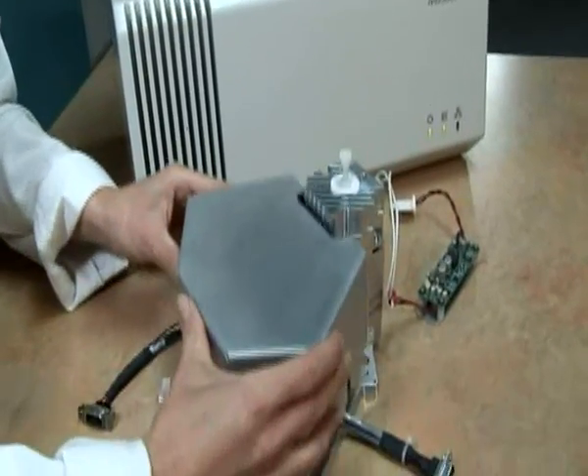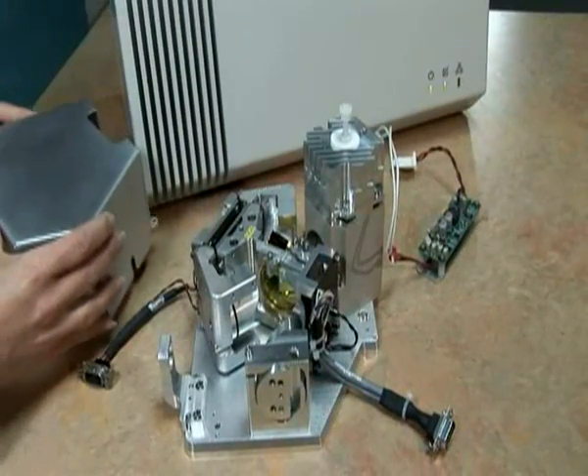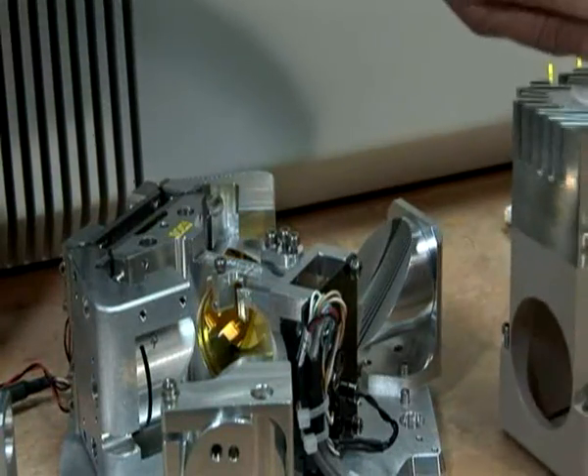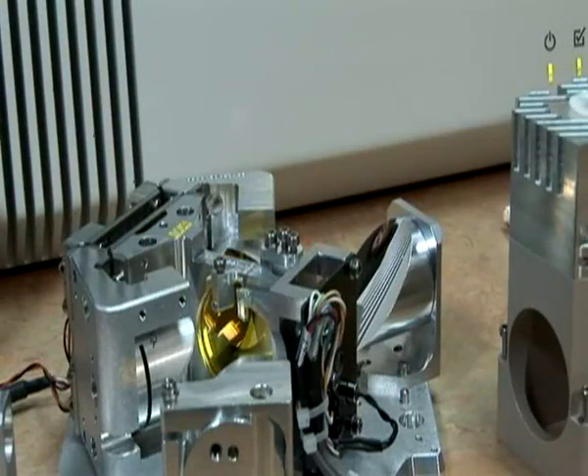The MB3000 is also designed to have very high stability. All the optics in the instrument are fixed in place — there are no adjustments anywhere in the optics — and as a result we obtain an extremely high level of stability in the instrument.